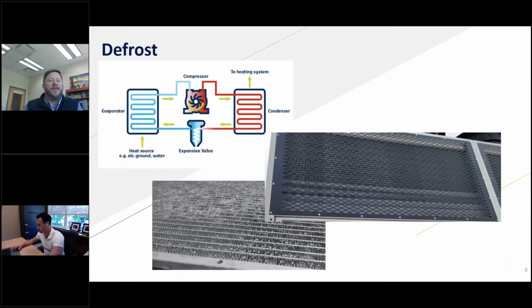So moving on to something that is different or unique to an air source heat pump versus what we might have done previously with a boiler setup, is the reality that we've got equipment sitting outside. If we look at my diagram in the upper left-hand corner, I'm showing that basic refrigeration system with the four major components: an evaporator on the left, your compressor in the middle, your condenser on the right, and your expansion valve or metering device.